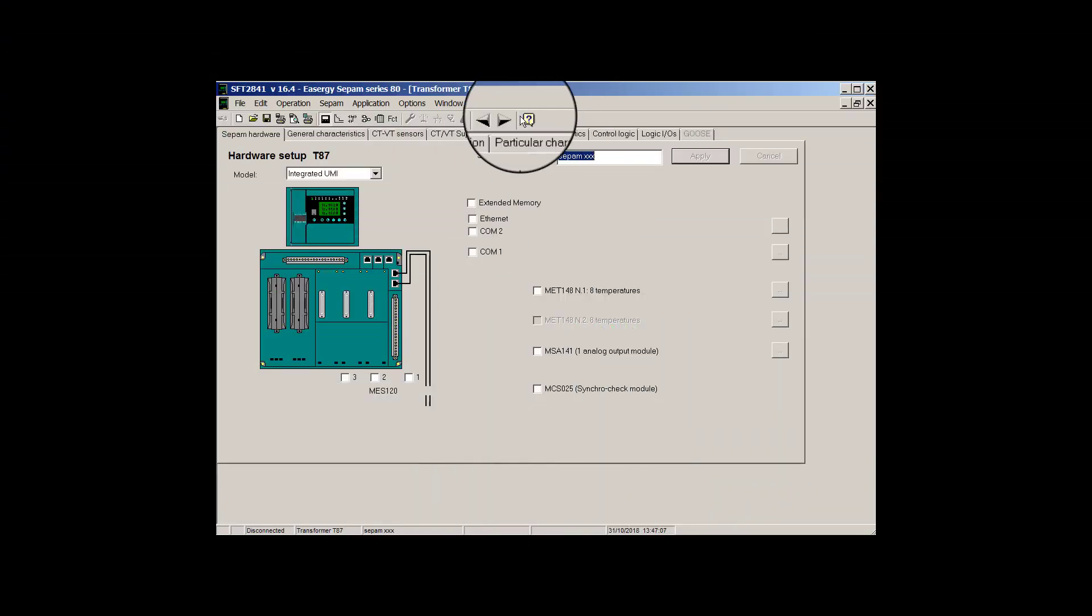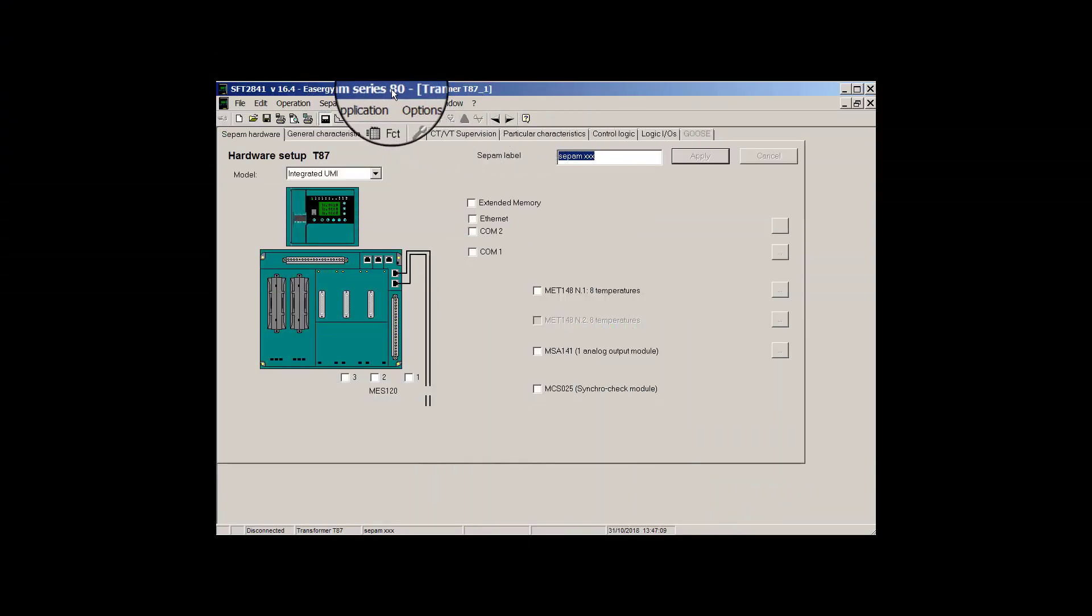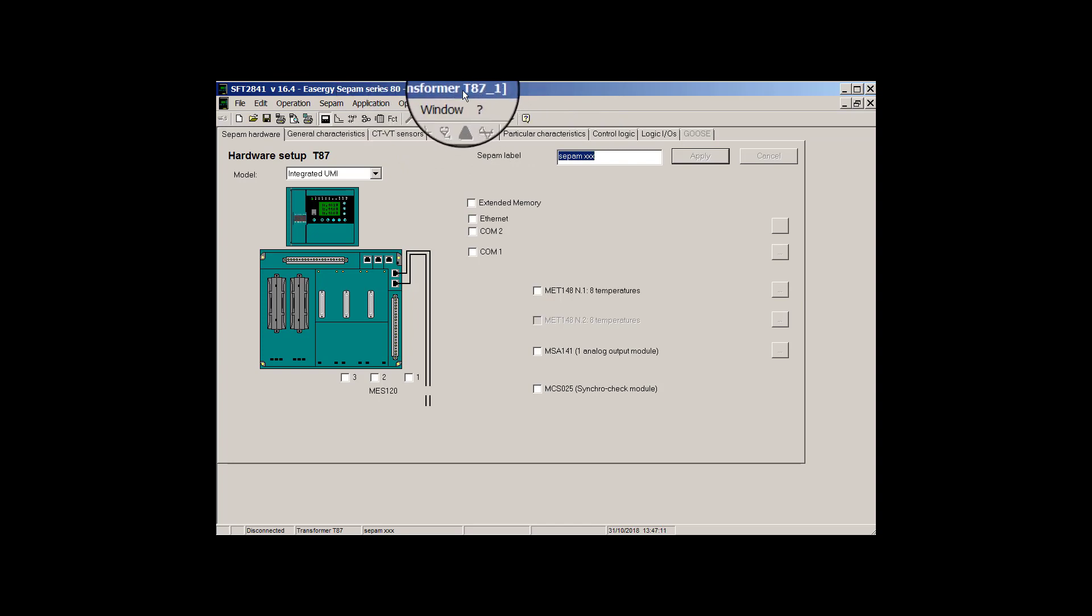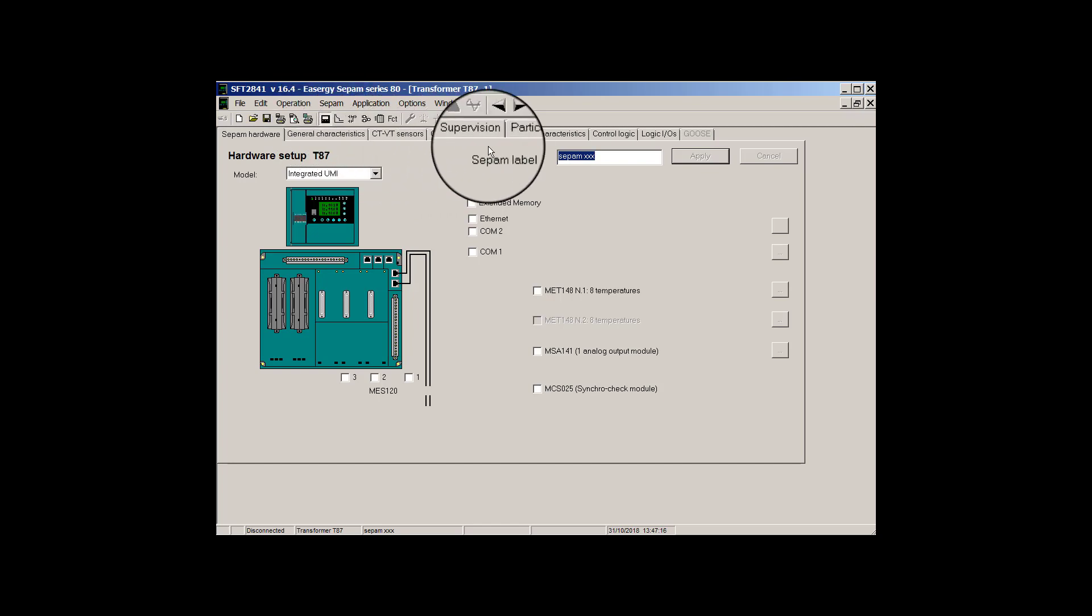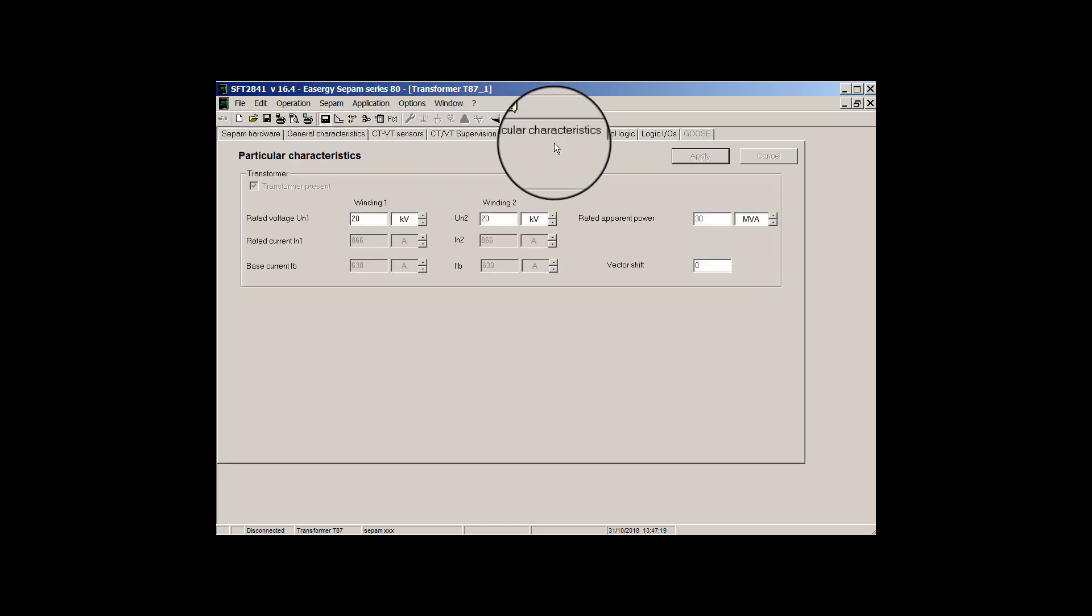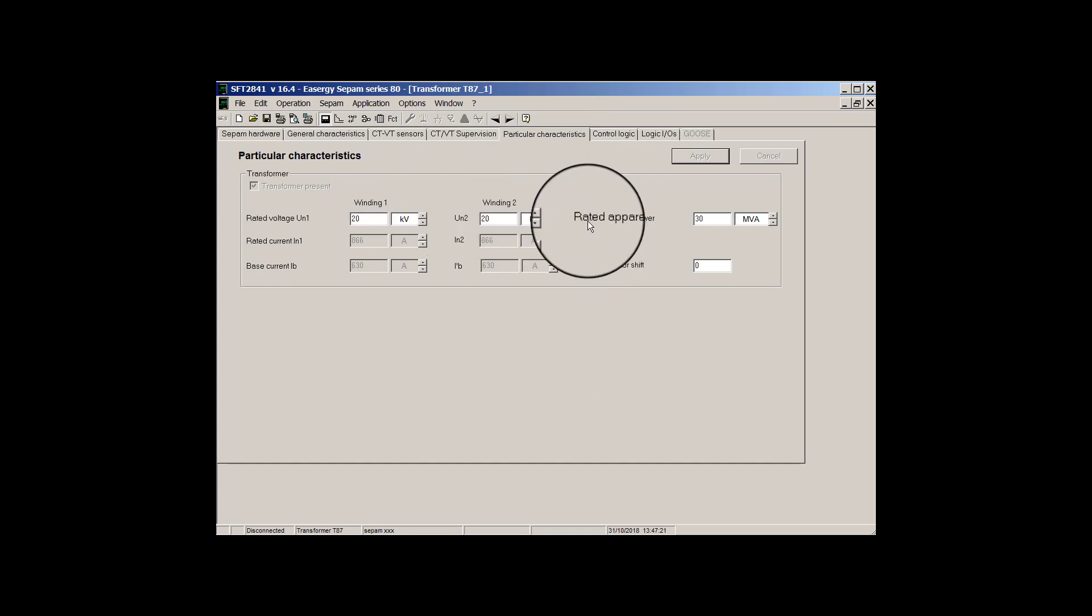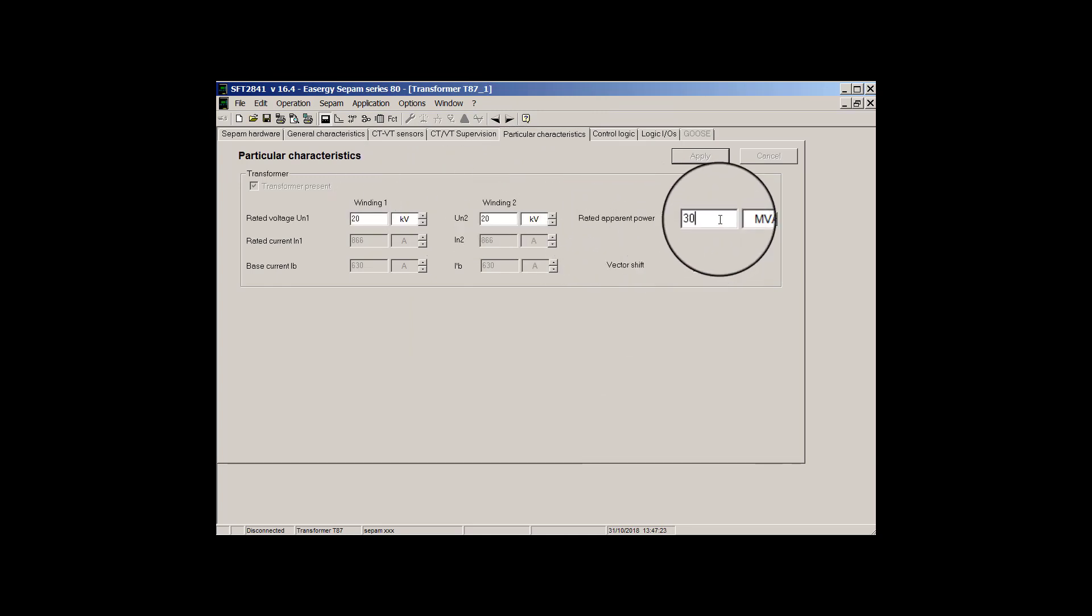Using SEPAM configuration tool SFT 2841, I'm going to explain. In SFT 2841, SEPAM series 80 model T87 is chosen. In SEPAM setting there is a part that we can set transformer particular characteristics.